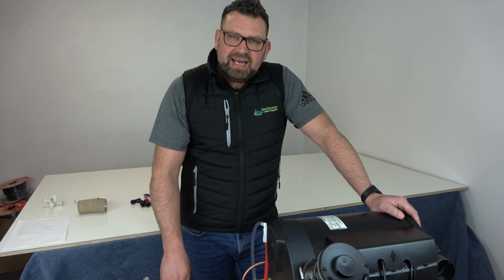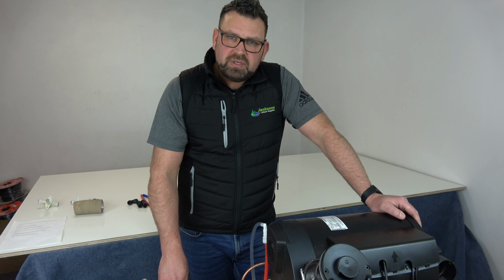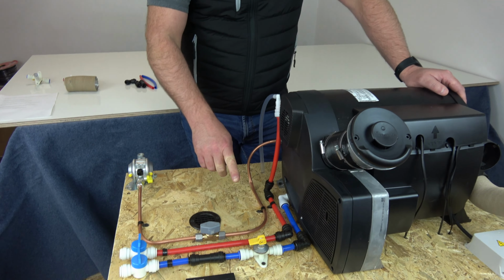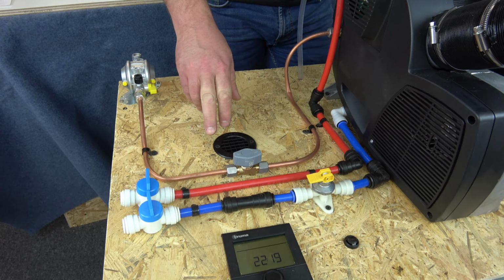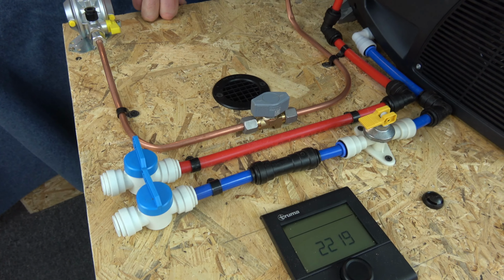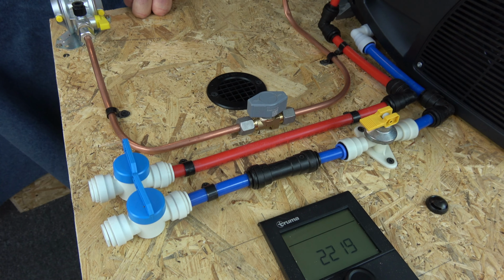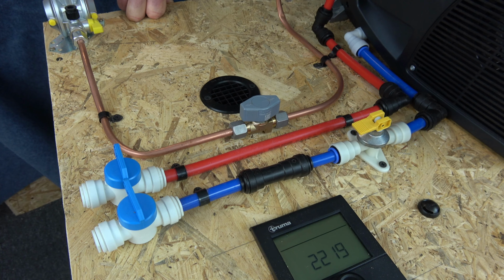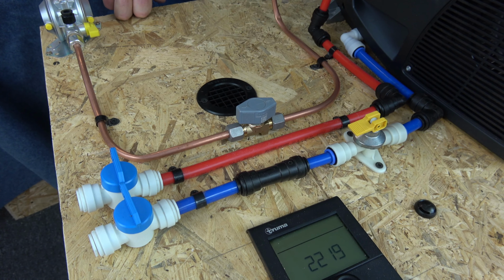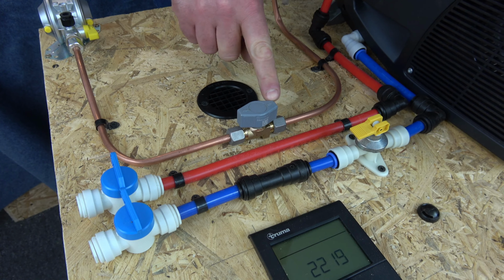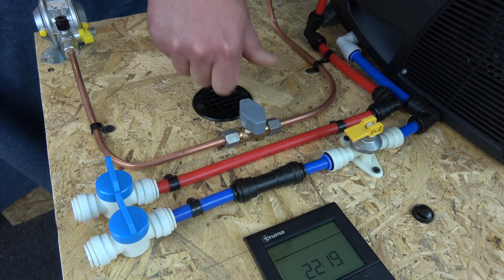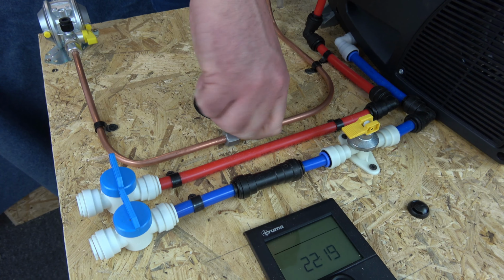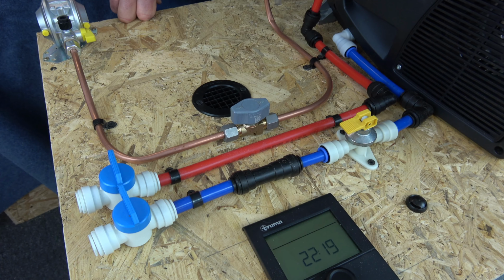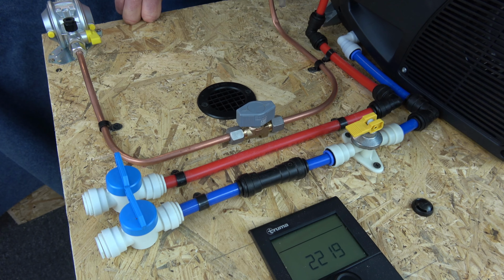Have a look at the gas connection on this Truma 4. So if we come down and have a look, we've got it in an 8mm copper. Now it must be fitted with copper and not with a flexi. We've popped an isolation valve in here. This is in the on position, this is in the off position. It's always good practice to have an isolation valve next or near to the boiler.